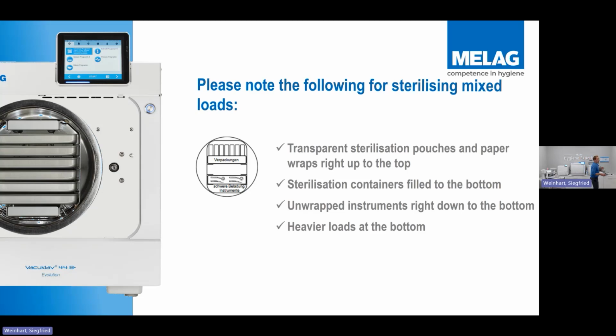Make sure that if we are using a mixed load, because with vacuum autoclaves, for example, they are indicated for pouched instruments, but we can run this rack inside of here, or we could even run the one inside of here as well, okay? Basically, we could have pouched instruments in here, or we could have unpouched instruments in here. They can all get run on a vacuum cycle.